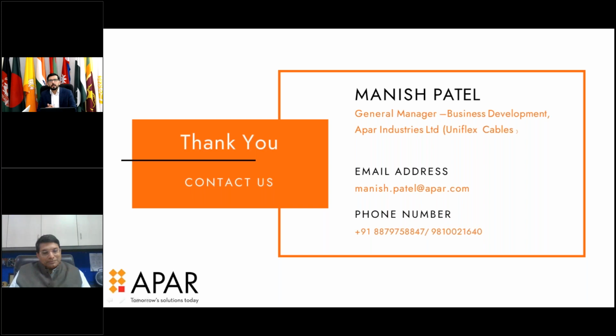The next question is also from Bhutan, for a 33 kV distribution system. They are using the covered conductor system. However, they are saying they had issues with slipping of the insulation, especially at river crossings. How can they address this issue?